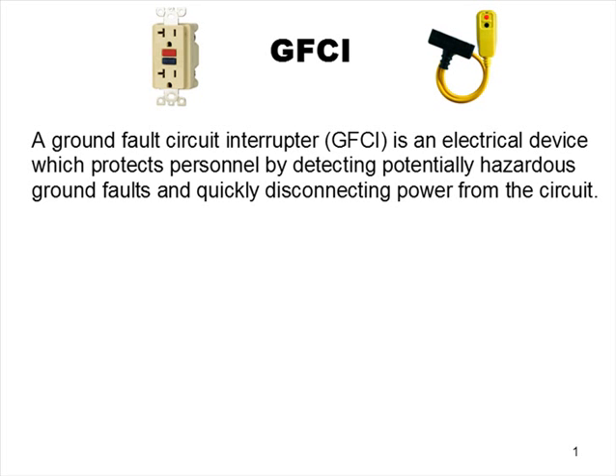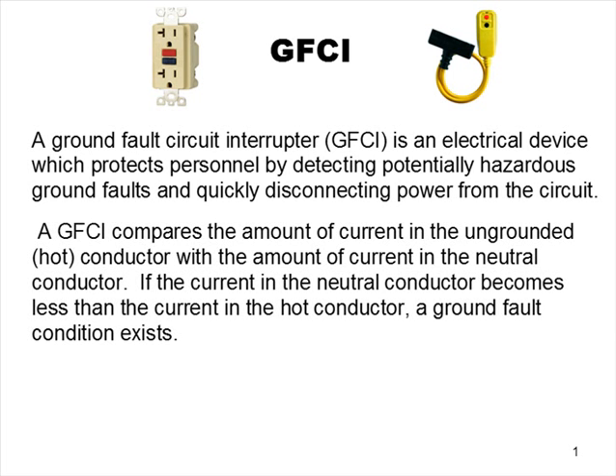And I mean quickly. A GFCI compares the amount of current in the ungrounded, the hot conductor, with the amount of current in the neutral conductor. They should be what? The same, right? If the current in the neutral conductor becomes less than the current in the hot conductor, where has it gone? Well, it's gone to ground. This is electricity. It's very definitive. 6.24 times 10 to the 18th power. Oh, wait a minute, there's two of them missing. Oh, they went to ground.